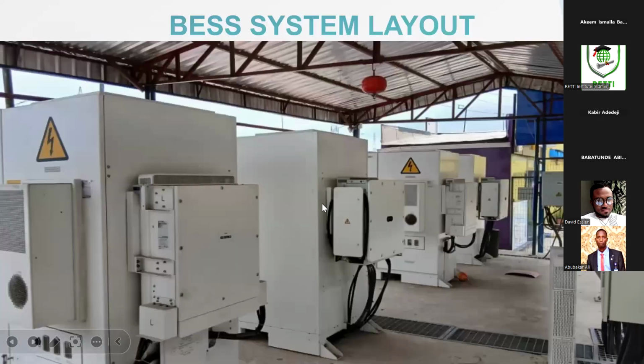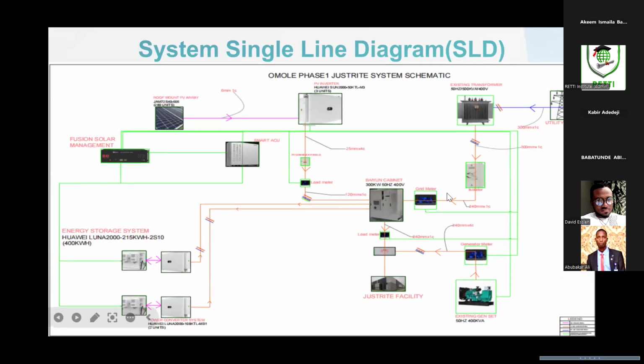So the controller supplies the aggregate of this, which now goes to the ATS. Then the one from the generator also goes to the ATS. So it's the ATS that will now supply the load. But the primary source is always this guy, except if any of the three sources are not available, then the generator comes in.